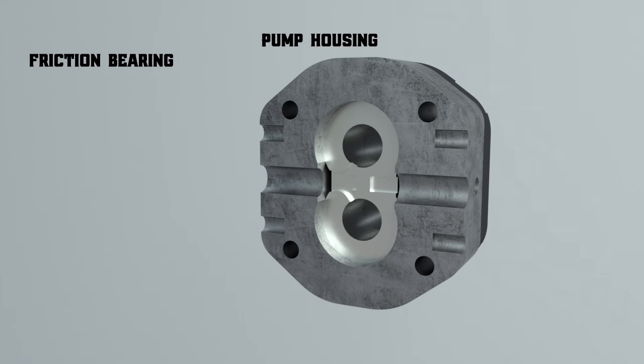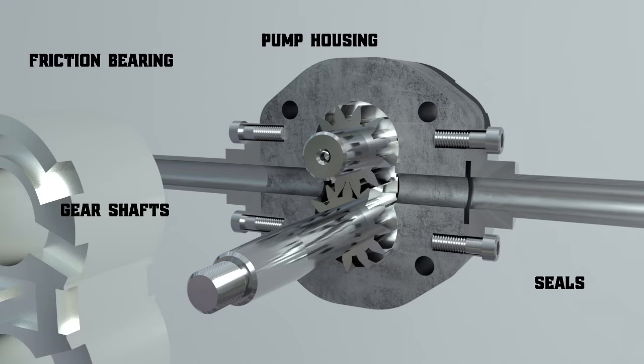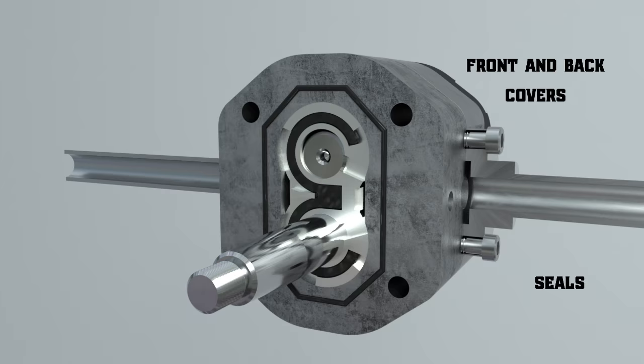They are seals to ensure the leak-proof separation of the suction and discharge channels. The front and back covers are bolted to the housing. The shaft sleeve and the rubber rings prevent fluid from flowing out of the pump.